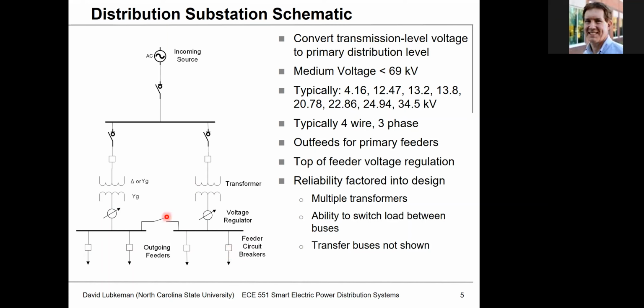Note that there's a tie switch between the two buses. Suppose the transformer on the left has to be taken out for service — there would be a disconnection switch, not shown here, that lets us transfer load from one bus over to the other. So this is what we have for this particular substation.